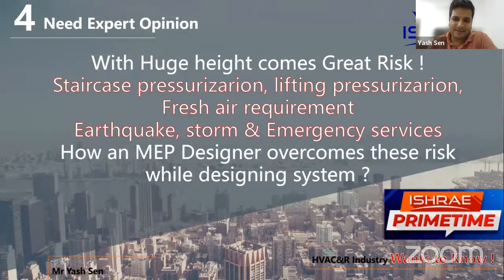For fresh air, Mr. Sagar mentioned the stack effect we see in high-rise buildings, where there's different temperature inside and outside, and therefore different pressure inside and outside the building. Because of this, there's always infiltration or exfiltration from the building. We have to consider all these factors while designing the system, because temperature is increasing day by day. We have to check all the leakages from the building and then design the system. Also, the fresh air requirement is affected since temperature is increasing day by day, and we have pollution in metro cities - around 1000 ppm sometimes in Mumbai.